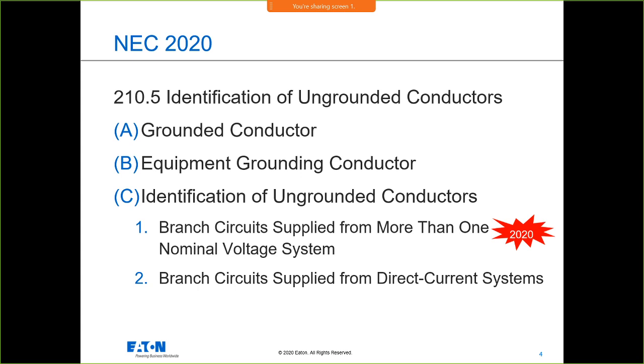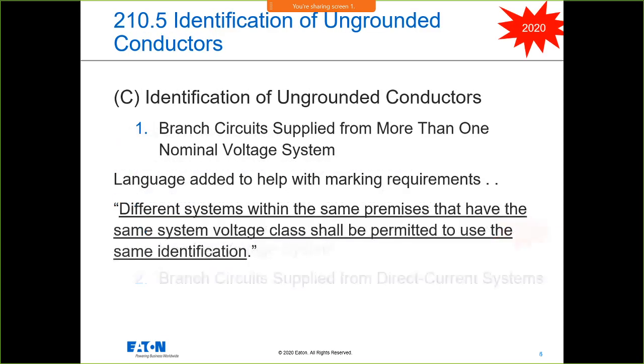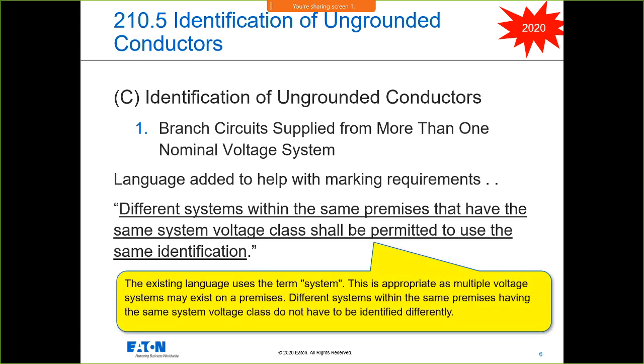Branch circuits supplied from more than one nominal voltage system. We did a change in 210.5C that talked about different systems in the same premises—different systems within the same premises that have the same voltage class shall be permitted to use the same identification. So we added some language to help add some clarity there. We didn't want people to think that the moment you introduce a new voltage, you have to now label everything in that facility. So that was the thought process behind what we did from a panel two perspective.